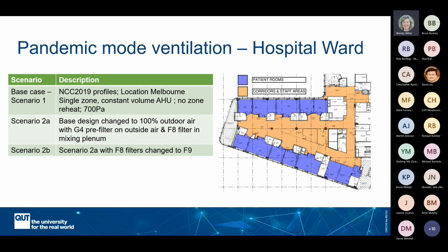So another set of modelling that was supported by AHIA's involvement involved investigating the energy impact of COVID-19 ventilation strategies. In particular, the early pandemic advice, and this was advice from the Victorian Health Department back in 2020, to increase outdoor air to 100% and increase filter efficiency to F9. So this was in line with the general ventilation mantras of dilution followed by filtration, and was common around the world at the time.